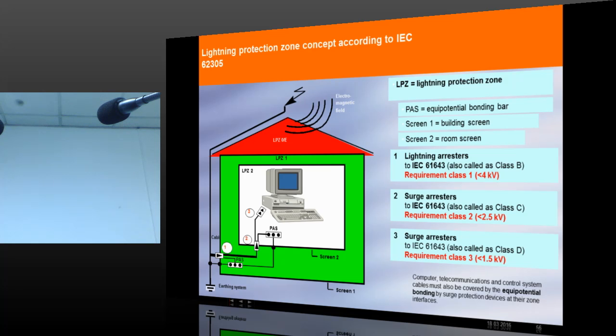So basically, if we are able to achieve the LPZ concept, we will be able to protect all the electrical and electronic equipment. And here you see, you need a surge protection device, you need one more surge protection device, you need one more surge protection device. The first one, purpose of this one is to divert the lightning current, which is in the form of 10 by 350 microseconds. That means this one is a very high level lightning current arrestor, lightning or a surge arrestor.